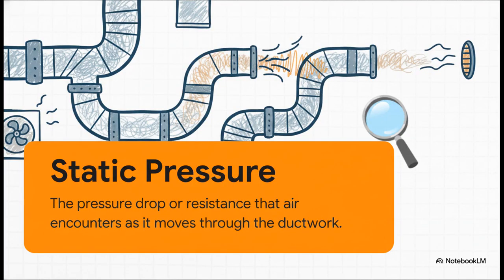Right, so all this resistance, this friction, in the engineering world, it has a name. It's called static pressure. Basically, it's the force that the fan has to constantly fight against, just to push the air where it needs to go. And if that static pressure gets too high, well, the air just isn't going to make it to those rooms at the far end of the line. And that's when you get those stuffy, uncomfortable spots.